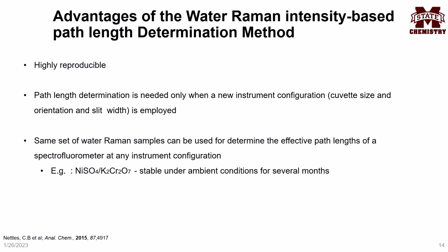The effective excitation and emission path lengths should be redetermined only when a new instrument configuration is used. Also, the same set of water Raman chromophore mixtures can be used each time.